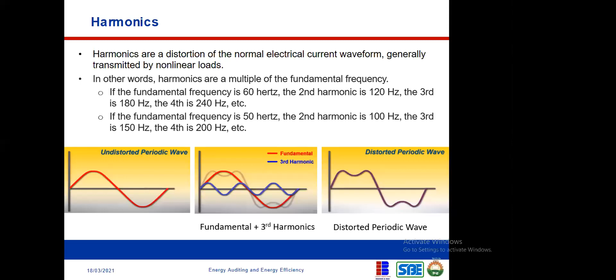We call this, in the electrical power system, harmonic pollution. Please go to the next one. So harmonics are generated by solid state based equipment such as switching power supplies in PCs, personal computers, DC drives, variable frequency drives, electronic ballast, arc welders, battery chargers, and UPS, and more. All of these are what actually induce harmonics into the electrical system.